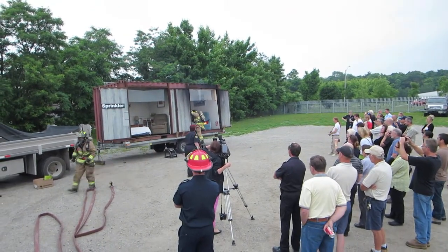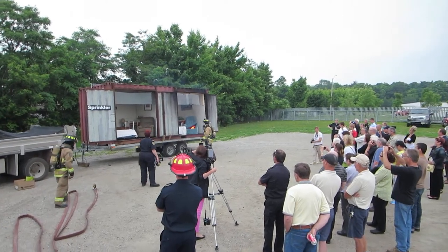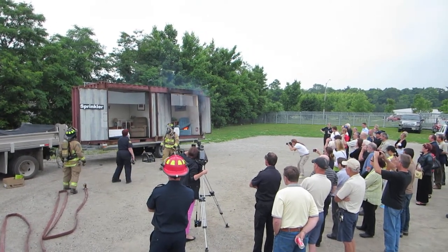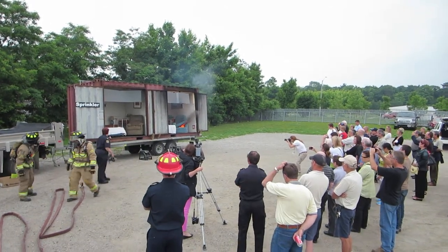That was three seconds of smoke — it's on the sprinkler side. The chair is just starting to ignite on the sprinkler side, and we've got a really good burn going on the non-sprinklered side.